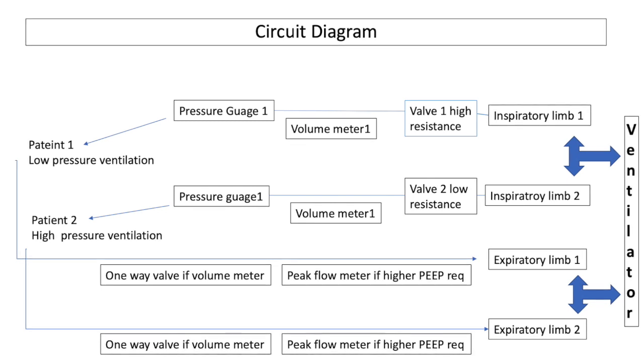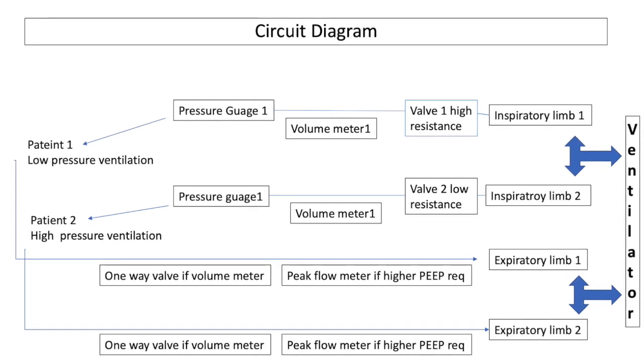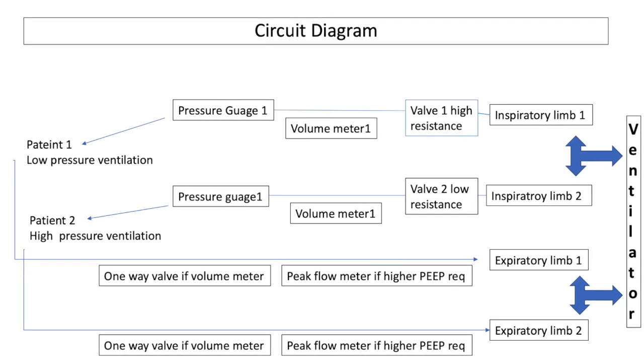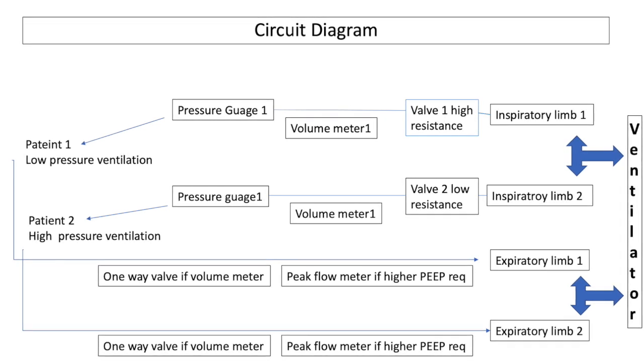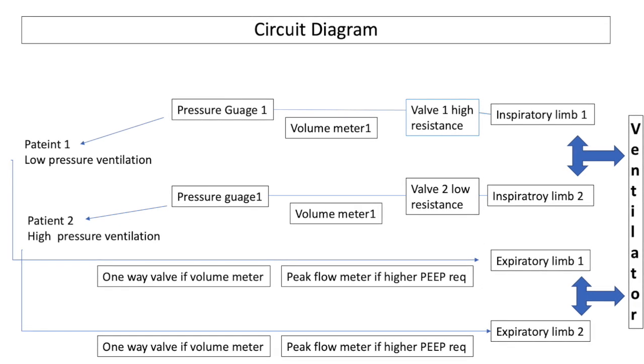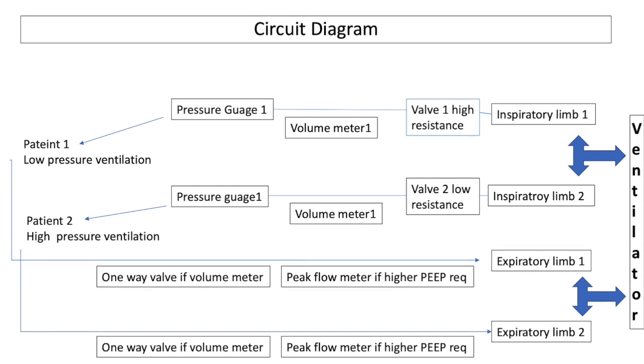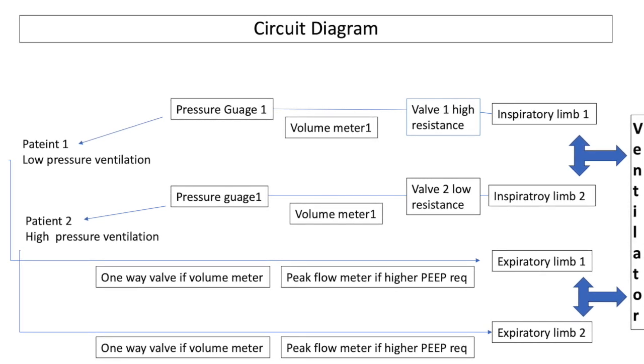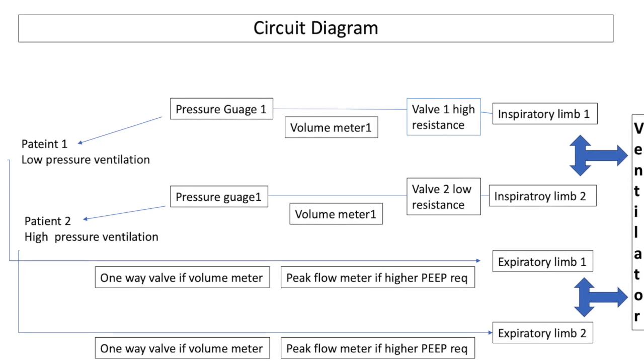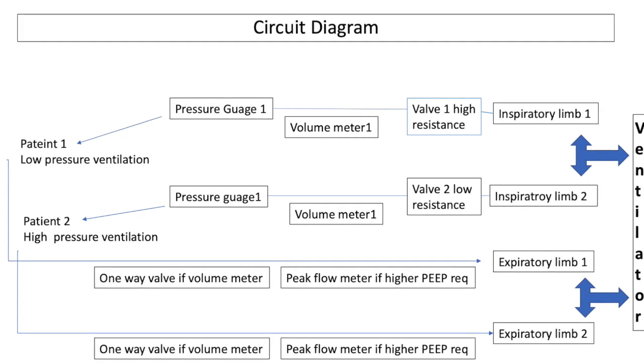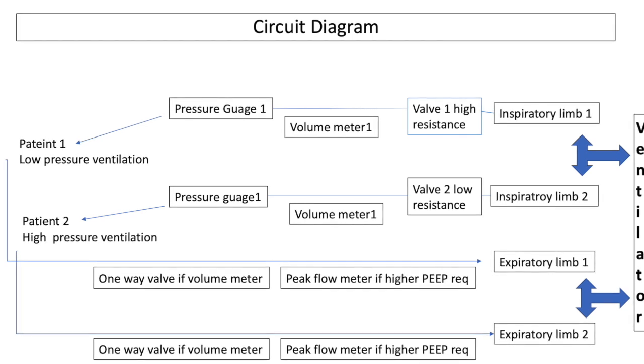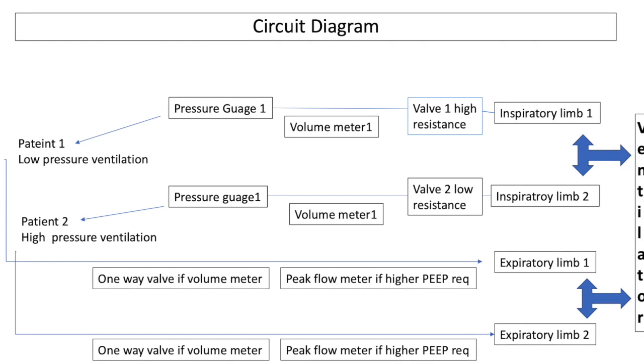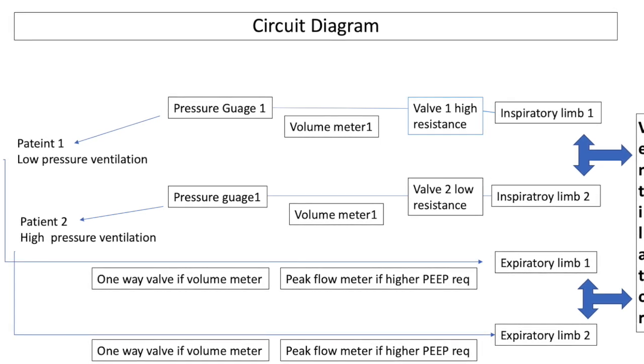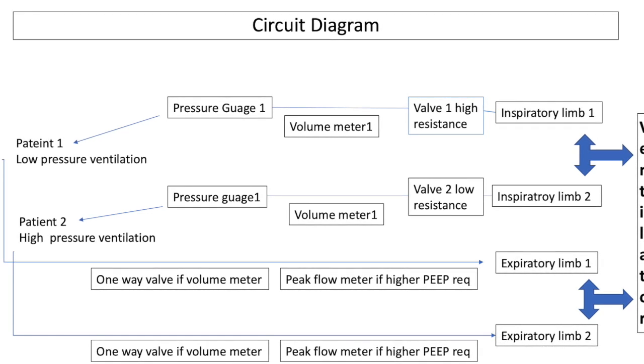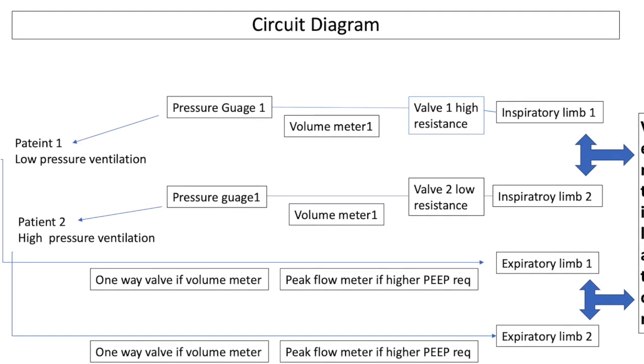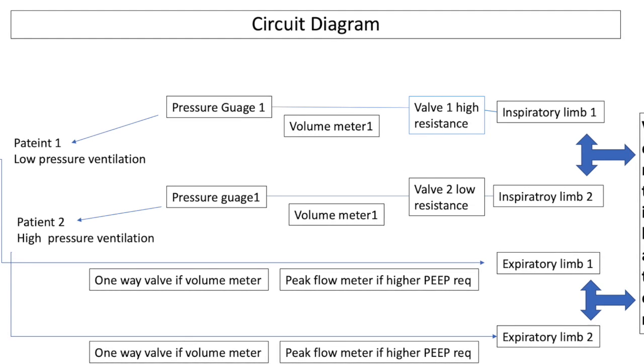At this time, I would also reach out to our engineering friends and see if we can modify the ventilators which have pressure flow sensors and combine them in one so that even if one patient's peak pressure goes high, the ventilator gives an alarm. That would be an ideal situation. I think this can be done by combining wires of multiple sensors into one and modifying either the output or the sensory alarm in the ventilator to go with the highest pressure. For our engineering colleagues, I don't think it should be that difficult to incorporate a pressure flow sensor and a valve which can measure peak and PEEP directly along with pressure and volume and set alarms based on specific parameters for individual patients. That would be a very small device and can work. This would actually solve the problem in the future if we again run into this unfortunate situation ever.